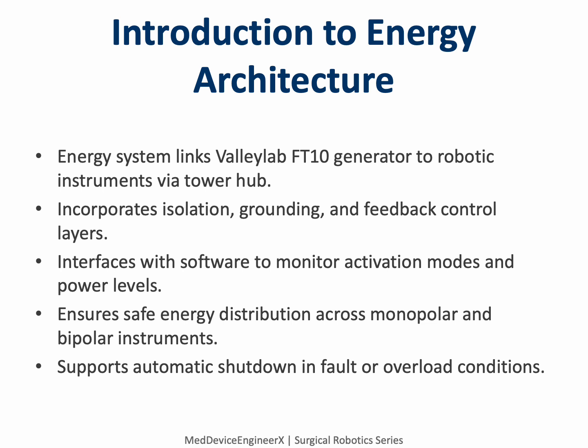Hugo's energy architecture acts like a vascular system for electricity, distributing, regulating, and protecting power across every instrument. The Valleylab FT10 generator forms the core, providing multiple modes for cutting, coagulation, and vessel sealing. It connects through the control tower to the robotic arm instruments using shielded cables and standardized connectors.